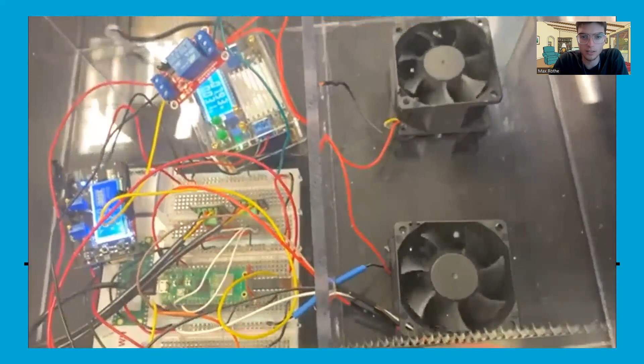In the unit that has the fans, we have an ultrasonic sensor, which is our safety feature. Essentially, we have a hood indicator, so that whenever this lid is opened, the fans automatically turn off, regardless of whatever the temperature reading is. And when it closes, they will turn back on only if the temperature is within the threshold.